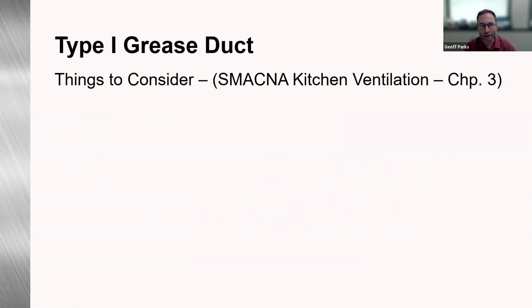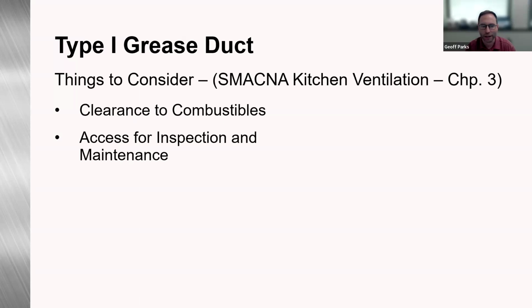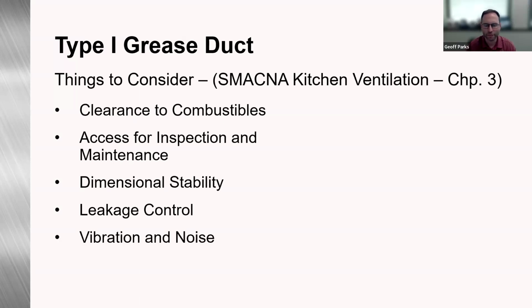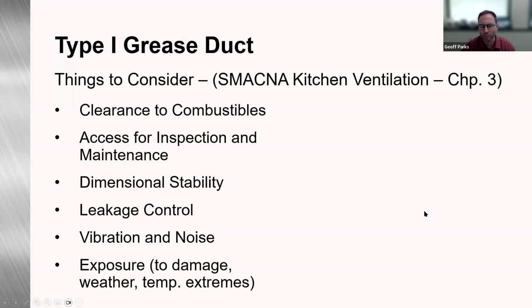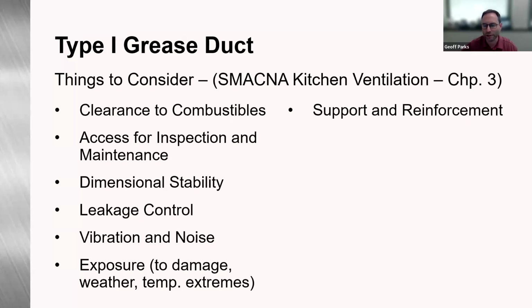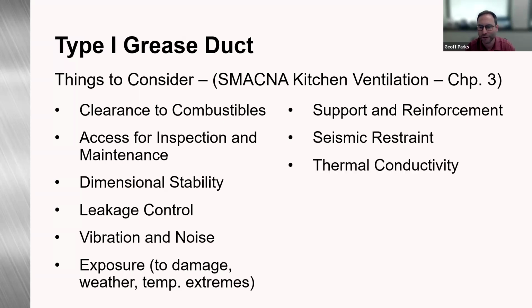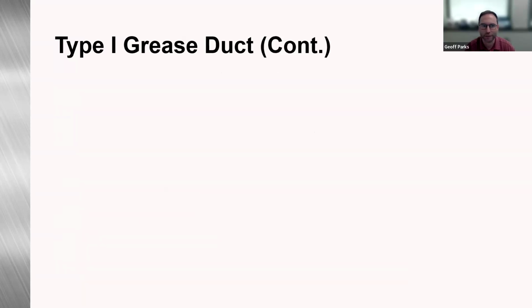So Type 1 grease ducts, some things to consider. These are out of the SMACNA kitchen ventilation, Chapter 3. Your clearance to combustibles, access for inspection and maintenance, obviously dimensional stability, leakage control, vibration and noise, any possible exposure to damage, weather, temperature extremes, and so forth. The support and reinforcement of that Type 1 kitchen grease duct system. Any seismic restraint requirements, those would definitely be defined within the project specifications. Any thermal conductivity.